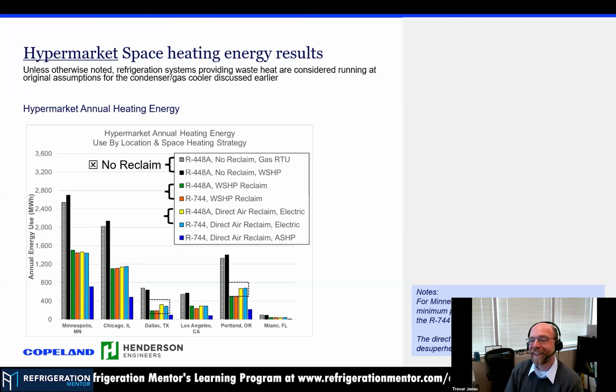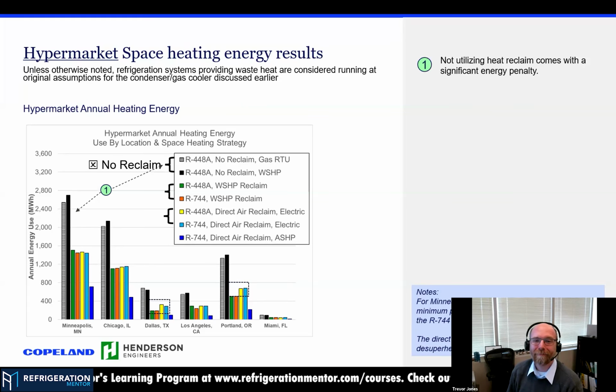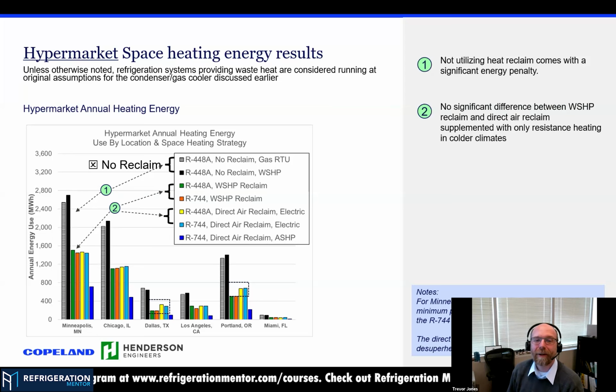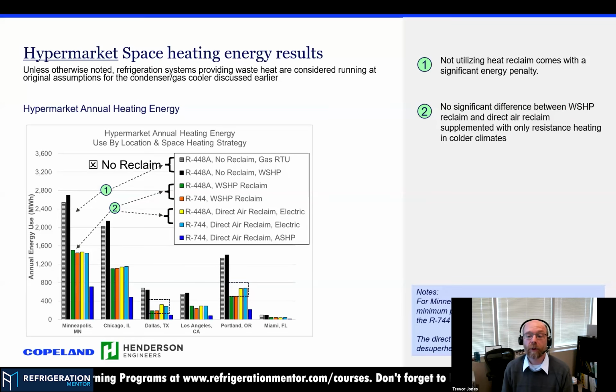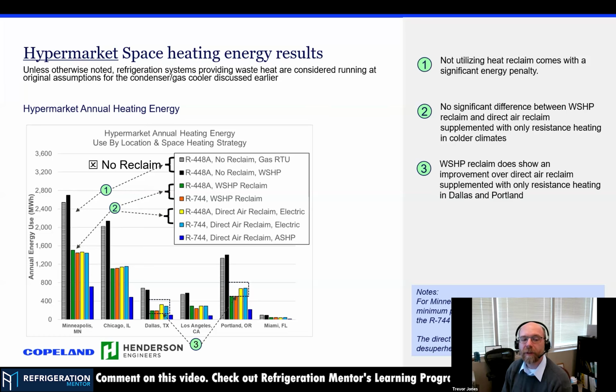So the hypermarket, when we looked at that, again we see that big penalty for no reclaim. But then when we start looking at water source versus direct, it kind of evens out because we need so much additional heat anyway that there isn't a huge benefit for the water source heat pump with no storage. If you have some way of storing heat, like injecting it into the ground in the summertime, this might change, but that's a little bit of a different system. There are still some areas where water source heat pump shows a bit of benefit, but those are in more mild climates like Dallas and Portland, where you don't have those very cold days that we're trying to provide the additional heat for.